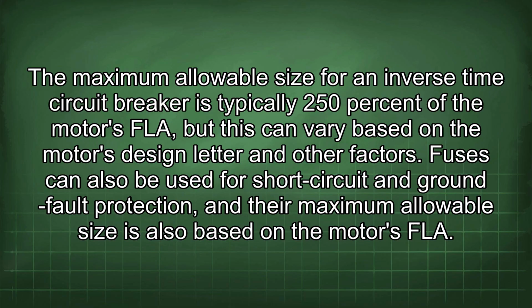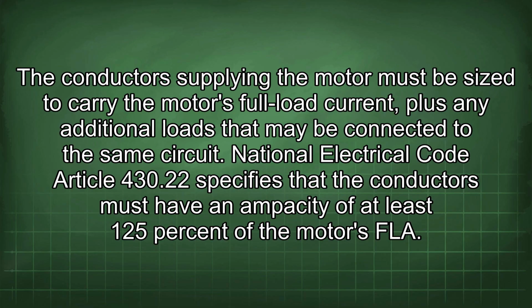The maximum allowable size for an inverse time circuit breaker is typically 250% of the motor's FLA, but this can vary based on the motor's design letter and other factors. Fuses can also be used for short circuit and ground fault protection, and their maximum allowable size is also based on the motor's FLA. The conductors supplying the motor must be sized to carry the motor's full load current, plus any additional loads that may be connected to the same circuit.